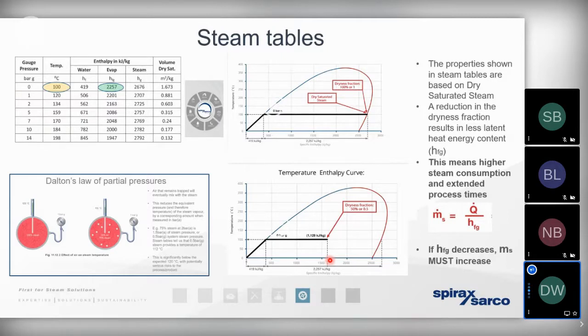So that means we could have a heat exchanger that is calling for more and more steam than the heat exchanger may be designed for. It's got to provide more and more steam to the process because it needs more and more energy. So the wetter the steam, the more energy is going to be consumed by the heat exchanger to provide the required heating effect of the process. Now, the thing to bear in mind there is if we're condensing more and more steam at the heat exchanger, there's more condensate that needs to be discharged across the steam trap and into the condensate network.